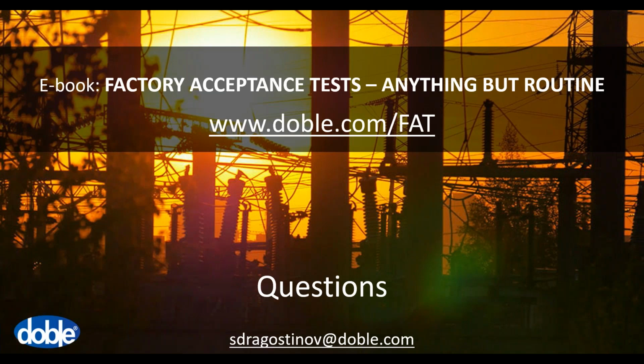Okay. So I suspect the next person has had a problem, which is why they're asking this particular question. In the event that a test is failed, for example apply voltage, but the supplier carries out repairs, how confident can we be in the long-term fitness for service if the test is passed when repeated? In such a situation, I would recommend a close investigation of the untanking process and also close following of the failure investigation and the root cause analysis. It depends very much on what the problem is, which parts are involved.